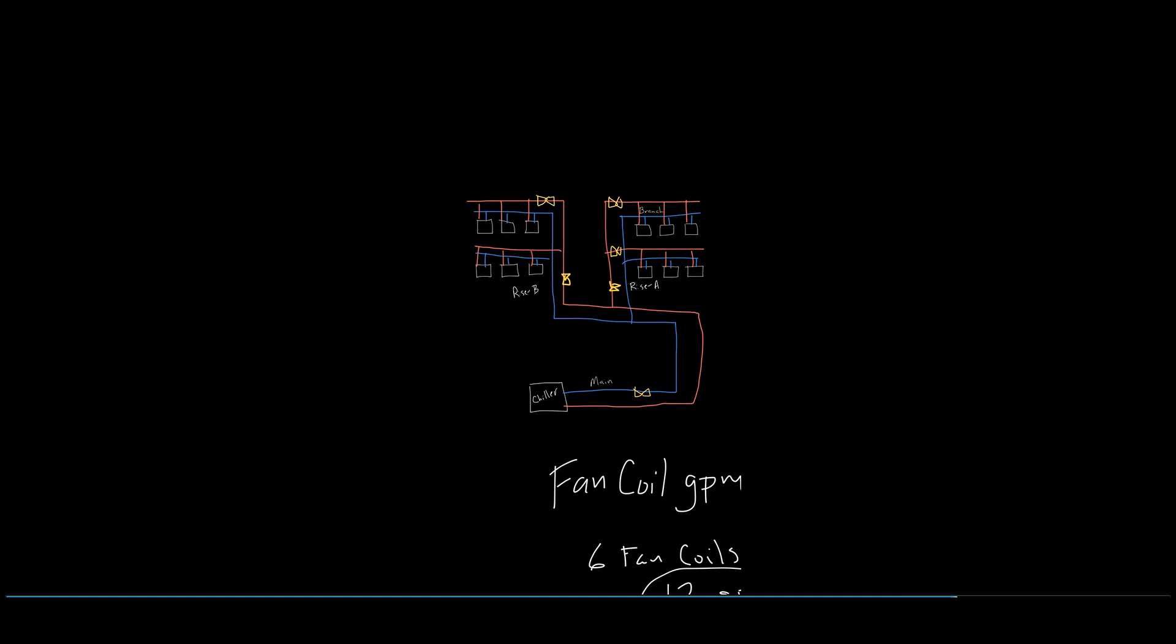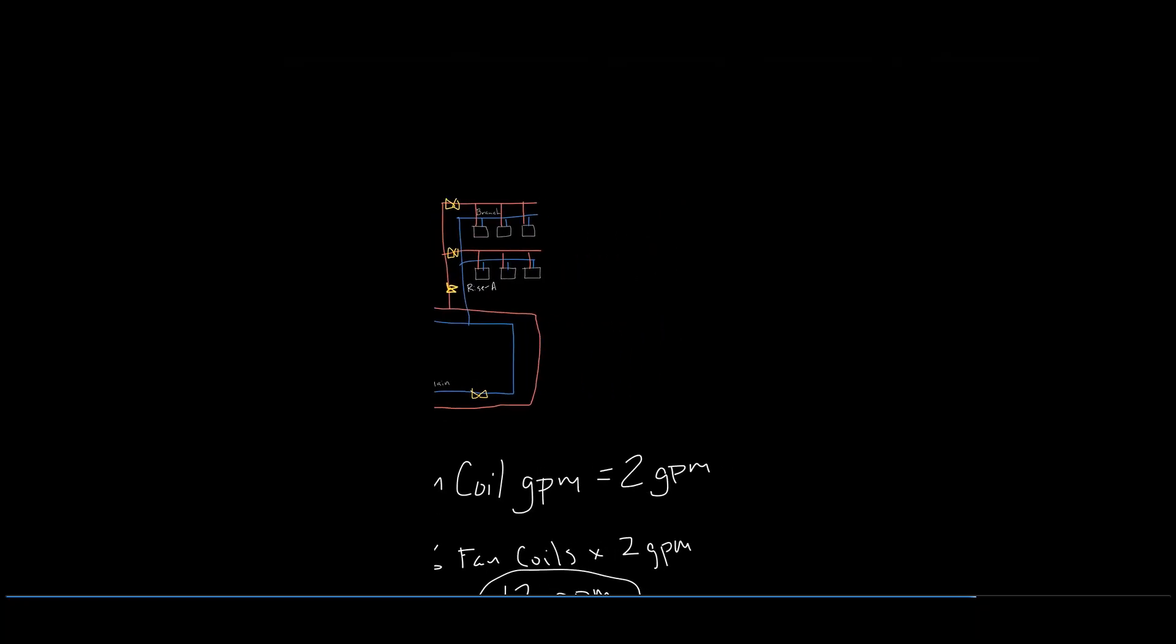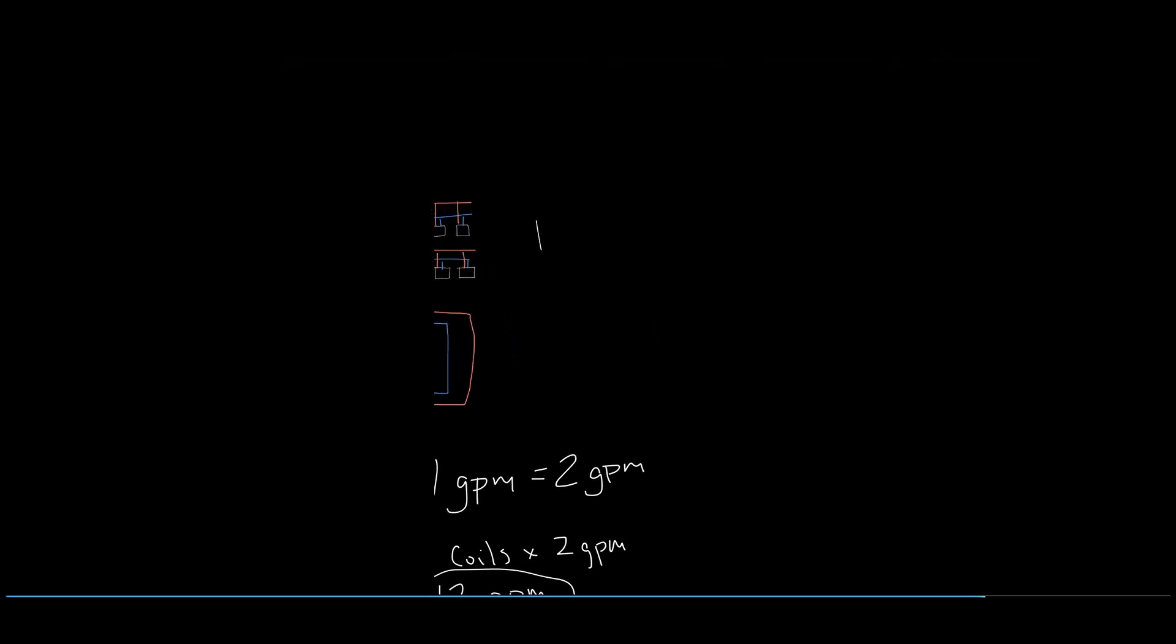Each branch return line will have its own balancing valve to ensure the flow rate is six GPM, which is three fan coils at two GPM.